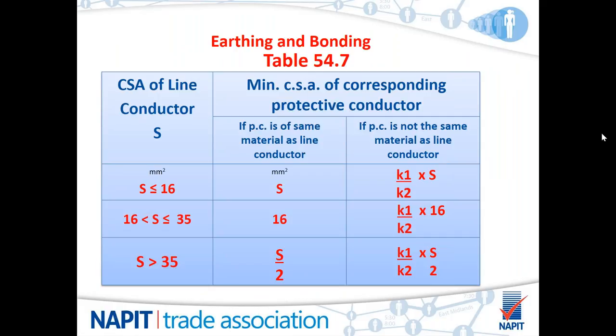Okay, so in the event that you are not using the adiabatic equation, you could also refer to table 54.7. As we can see, if the cross-sectional area of the line conductor is 16 mil or below, then the protective conductor should essentially be the same. In the event you are installing a cross-sectional area for the line conductor of 16 to 35 mil, again, your protective conductor would be 16 mil. In the event you're installing line conductors that are 35 mil or above, essentially you would take the cross-sectional area of that line conductor and divide it by 2, i.e. half it.